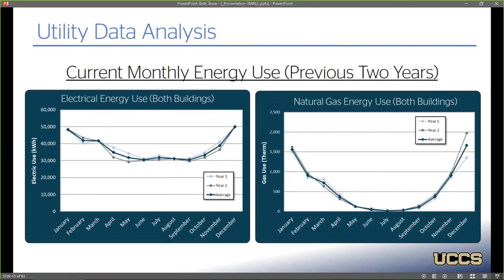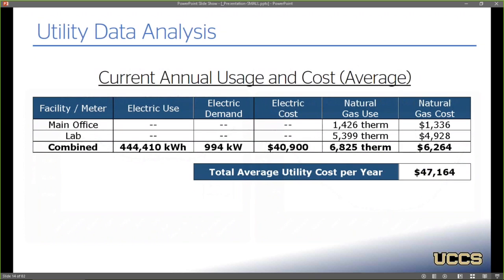So I looked at their previous 2 years of usage and plotted the average alongside those. You can see they're fairly consistent from the last 2 years, which suggests they haven't made a lot of operational changes within that time frame. In their total use, it's about 440,000 kWh, 6,800 therms. With their utility costs, there's a strong dominance of electric costs of about 41,000 out of the 47,000 total, which makes sense since they have electric heat, and that's going to be a huge component of that energy use.